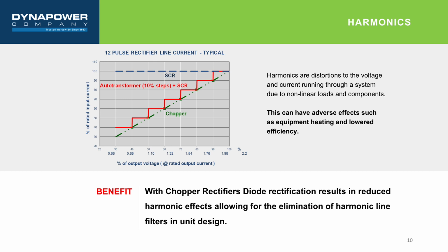Harmonics. Harmonics are distortions to the voltage and current running through a system due to nonlinear loads and components. Harmonics can have adverse effects, such as equipment heating and lowered efficiency, increased design requirements for rectifier transformers, and a need for compensating equipment. Harmonic voltages and currents are integer multiples of the fundamental frequency. For instance, on a 60 Hz supply, the 5th harmonic is 300 Hz, the 7th harmonic is 420 Hz, and so forth.